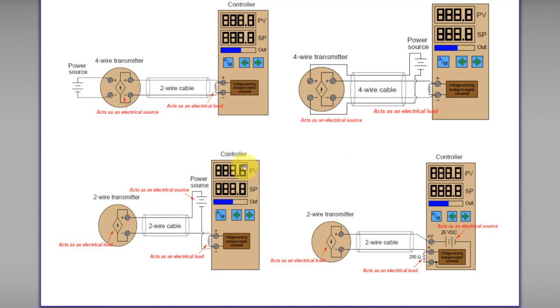How about this one? Again, this controller acts as an electrical load, judging by the positive and negative terminal here. Because the controller acts as an electrical load, the transmitter has to act as an electrical source. However, this is a two-wire transmitter instead of a four-wire transmitter. The transmitter does not have the ability to power up the loop, so it must be powered from an external power source. To solve this problem, this two-wire transmitter is externally connected to an external power source. This external power source is connected in series with the transmitter and the controller, so the power source here will power up both the transmitter and the controller.